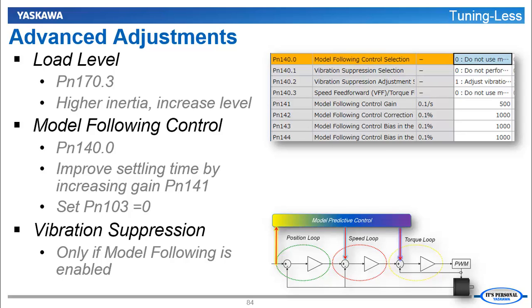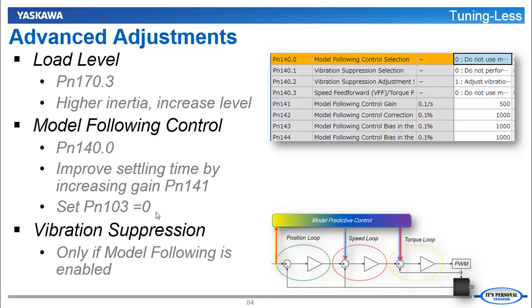Another one that's pretty advanced is called Model Following Control. Model Following Control can be turned on in the PN140s. We do not have it on right now. It's very important though that if you try to force on Model Following Control, that you set this inertia parameter 103 to 0. Regardless of what your inertia really is in this system. Also when you use Model Following Control, then that feed forward parameter you set previously it has no effect. Instead you'll be setting the feed forward of the Model Following Control algorithm. Using the Model Following Control gain. You'll be increasing this value.